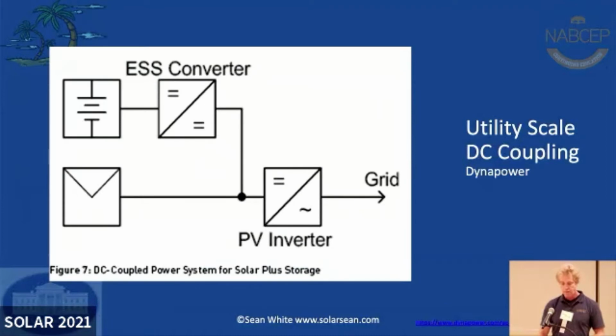And if you have DC coupling, what we have here is the PV, and I could charge the battery all with direct current without converting. So there's less conversion losses, but probably you have to have everything the same brand, or things have to work together that way. But less conversion losses is pretty good. And then another thing is fewer inverters. I only need one inverter there. So that's a different benefit. And this is a symbol for a DC to DC converter. So this particular one, we're calling DC coupling.